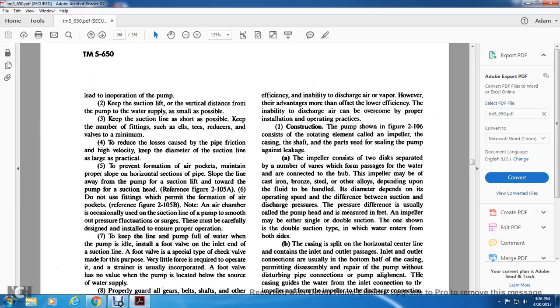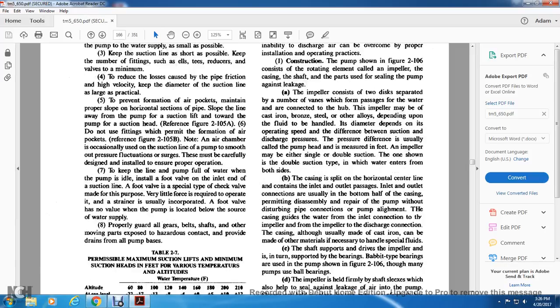Do not use fittings that permit the formation of air pockets. Reference figure 2-105B. Note: An air chamber that is occasionally used in the suction line of the pump to smooth out pressure fluctuations and surges must be carefully designed and installed to ensure proper operation. Seven, to keep the line and pump full of water when the pump is idle, install a foot valve at the end of the suction line. The foot valve is a special type of check valve made for the purpose. Very little force is required to operate it, and a strainer is usually incorporated. A foot valve has no value when the pump is located below the source of the water supply.